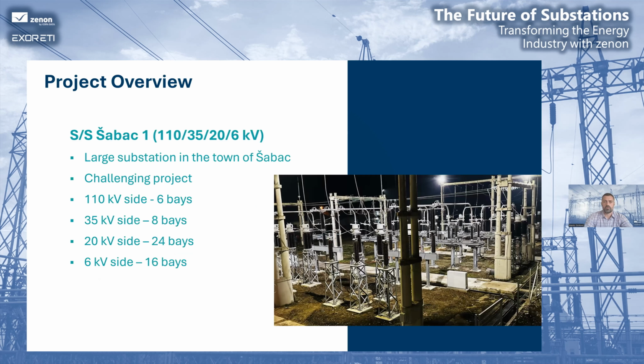Now I would focus on substation Šabac 1, one of our key projects in the last year. This challenging project required us to deliver a high level of customization and precision while finalizing the HMI. It is a large and complex facility with 6 bays on the 110 kV side, 8 bays on the 35 kV side, 24 bays on the 20 kV side, and 16 bays on the 6 kV side. I will share some specific details about the project later.